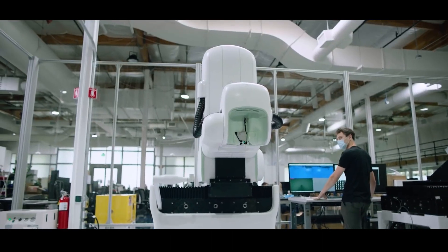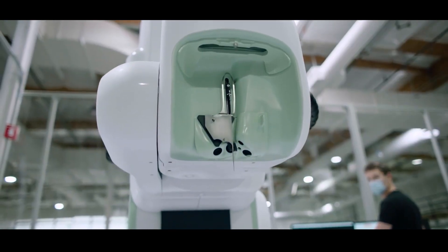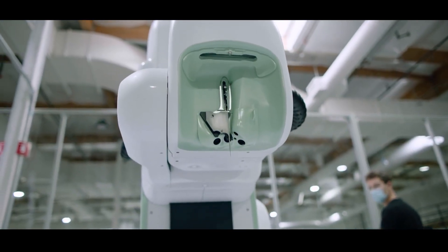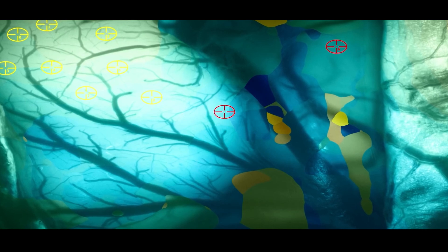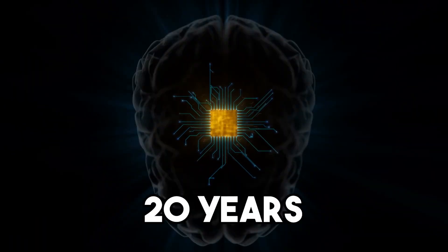The company has high-density testing racks and cabinets full of devices undergoing accelerated life testing at various stages. To prevent low-frequency edge case failures from occurring inside a human subject, they want to identify them. The intended lifespan of a Neuralink implant inside a person's skull is at least 20 years.